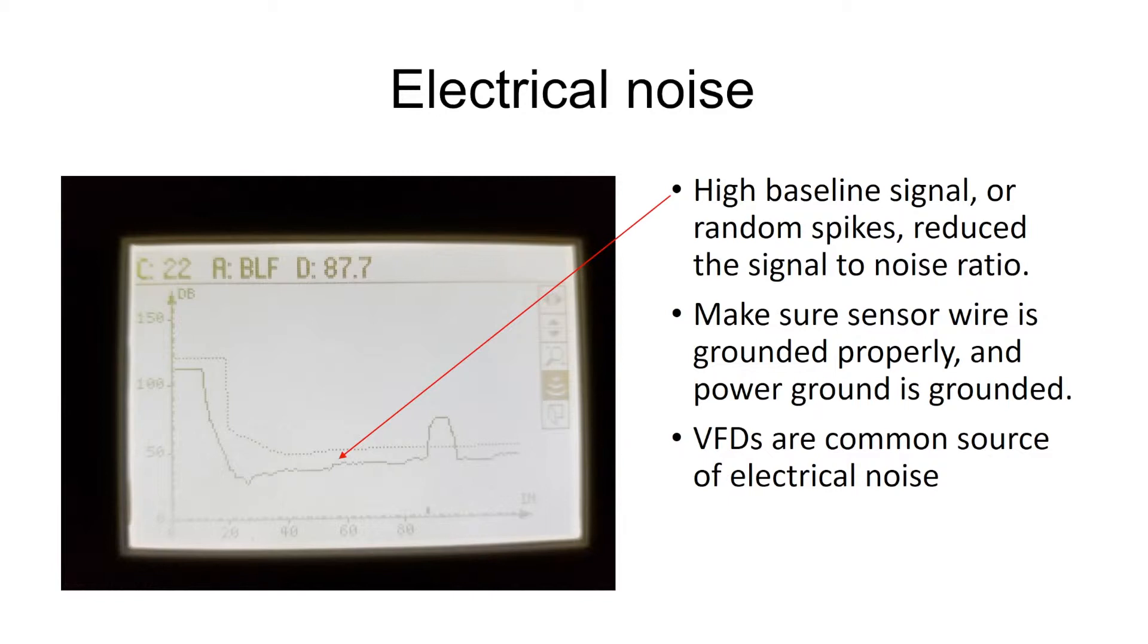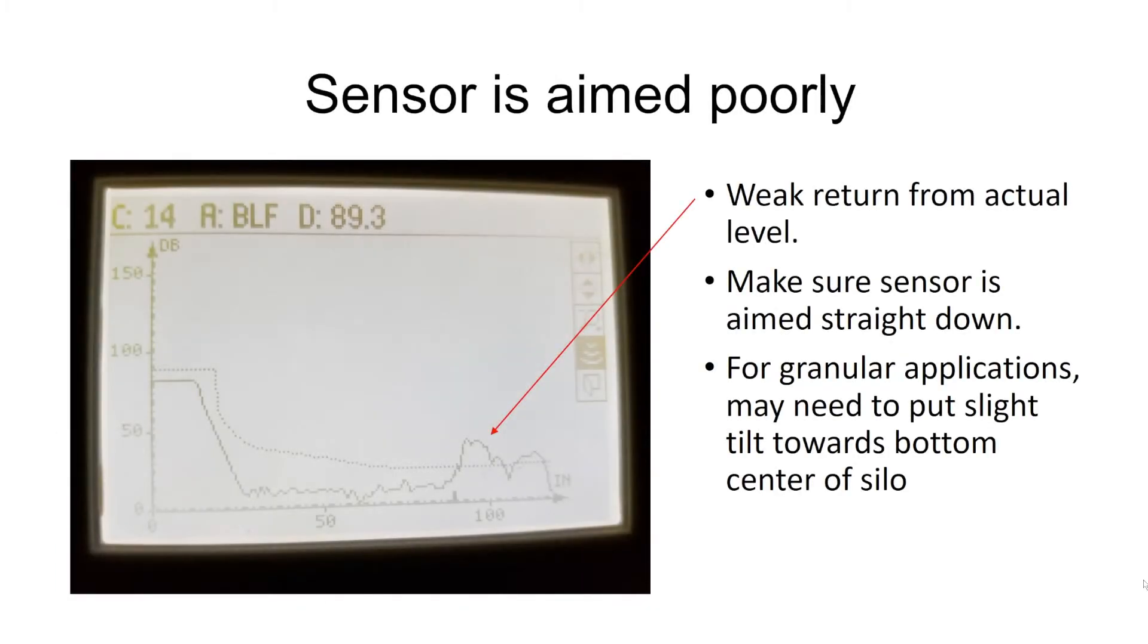So, if possible, I want to make sure that the VFDs are wired right using the correct type of wire, they're filtered correctly to try to reduce the amount of noise, and also, I want to make sure that the sensor, the ultrasonic sensor wire is not in the same conduit as any type of AC power line. I want to keep that separate from any of our noise generating lines.